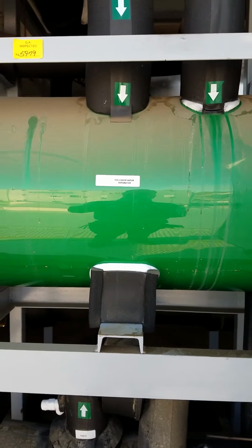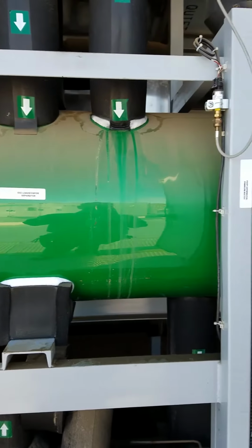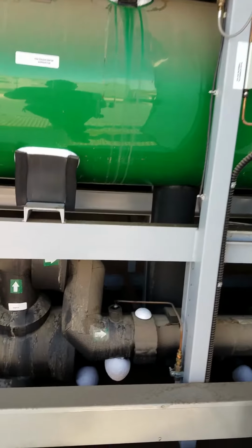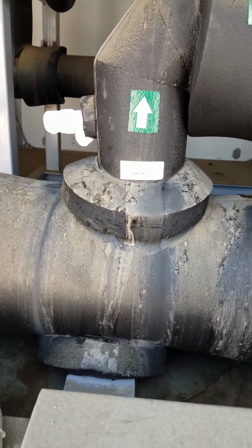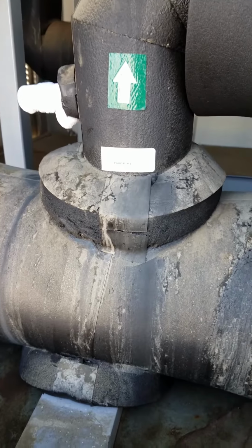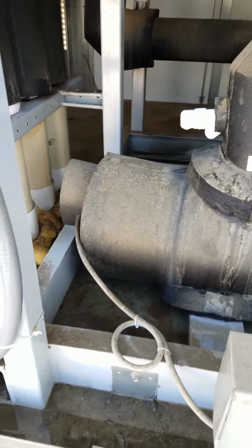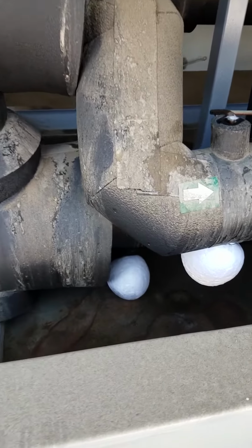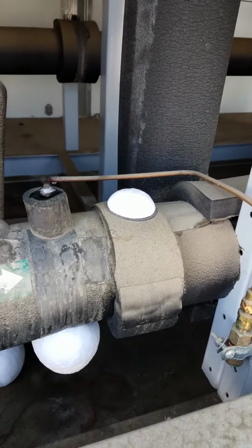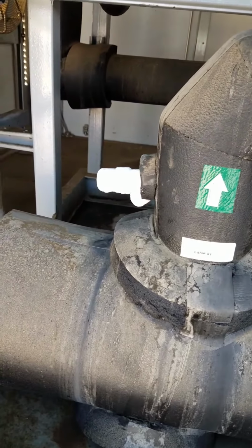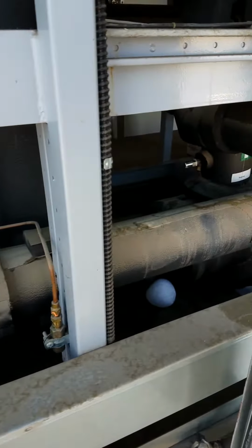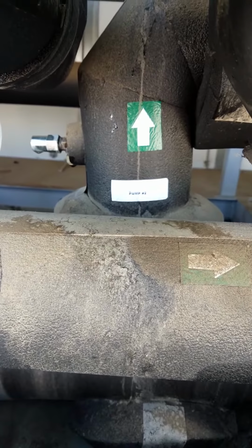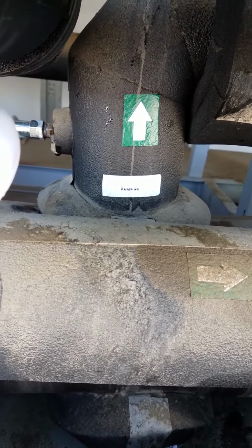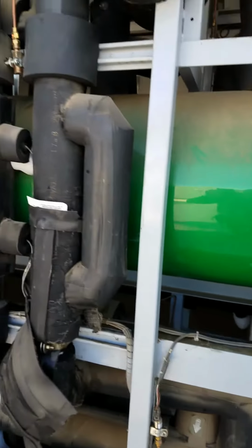There's a separator inside. It separates the vapor from the liquid CO2. Down here you got your pump 1. All insulated, because if it's not, it'll turn into a big ball of ice like the areas that are not insulated. CO2 runs very cold. Then on the other side, we got pump 2. I don't think you can focus in back there, but there's a pump 2, again all insulated.